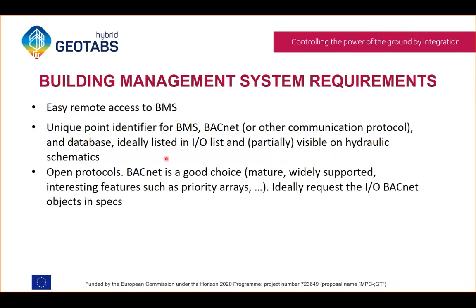It's important to use open protocol. You have seen at the beginning of the presentation that thanks to the fact that the BMS supported BACnet, it was fairly easy for us to connect to the machines by simply bringing a computer on site and communicating through BACnet. If you use a proprietary or closed protocol, this is not going to be possible.